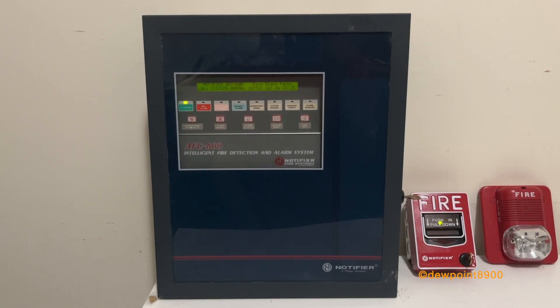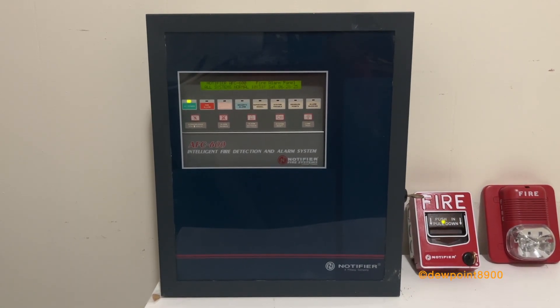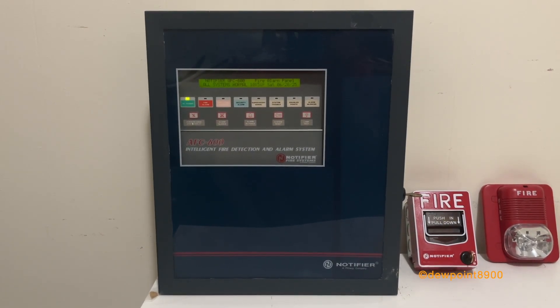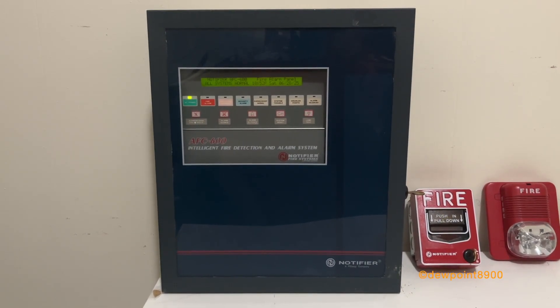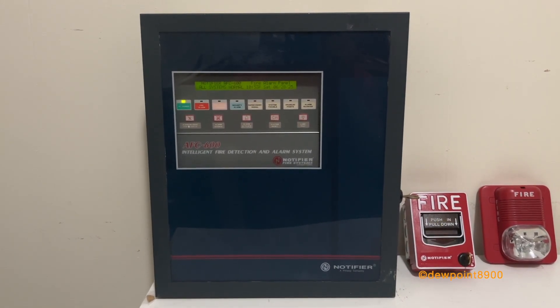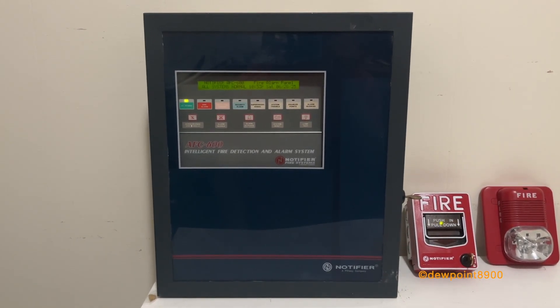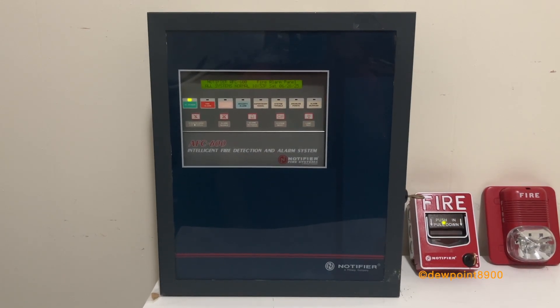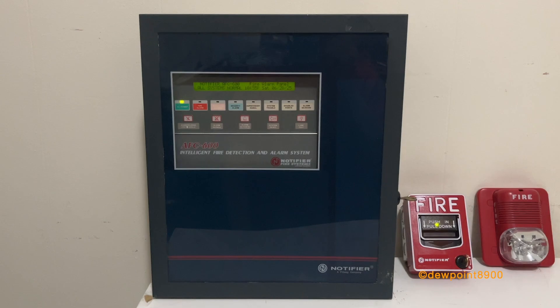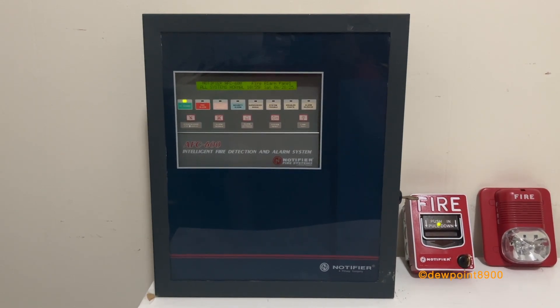Hello everyone. This is a Notifier AFC-600 Fire Alarm Control Panel. These were first introduced in the late 1990s and were designed for small to medium-sized facilities. At its core, the AFC-600 is an AFP-400, but it introduces a new addressable protocol known as FlashScan. The Notifier AFP panels use System Sensor's classic loop interface protocol, otherwise known as CLIP.